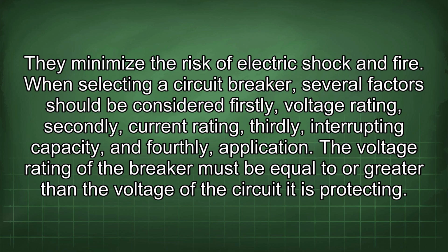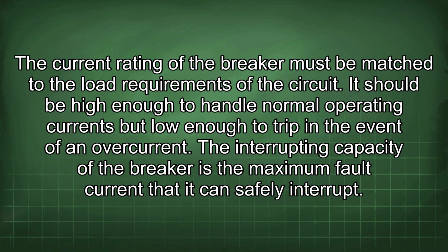When selecting a circuit breaker, several factors should be considered. Firstly, voltage rating. Secondly, current rating. Thirdly, interrupting capacity. And fourthly, application. The voltage rating of the breaker must be equal to or greater than the voltage of the circuit it is protecting. The current rating of the breaker must be matched to the load requirements of the circuit.